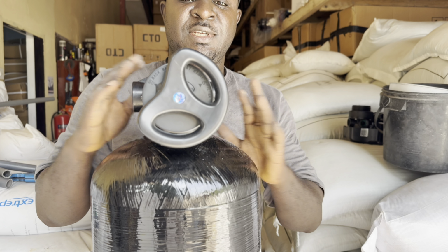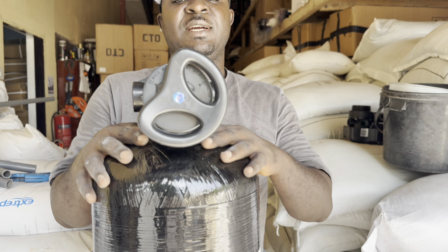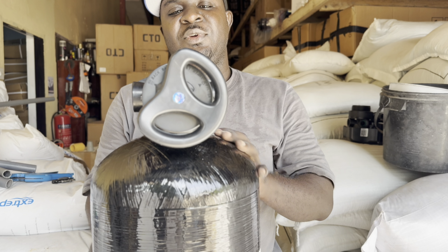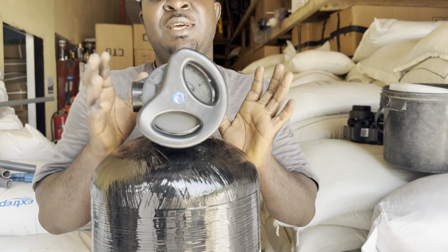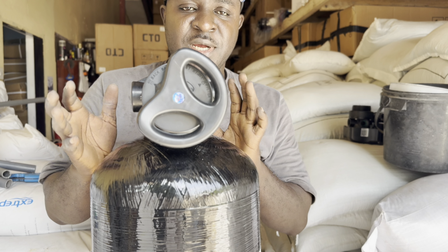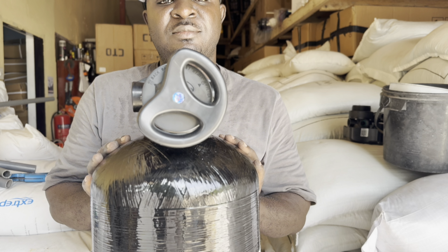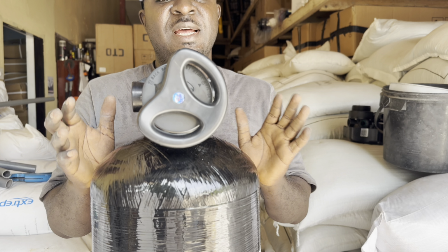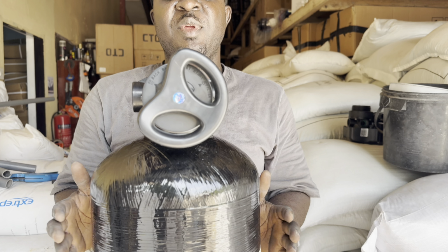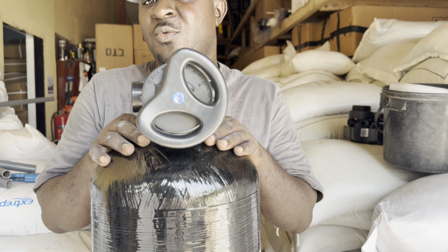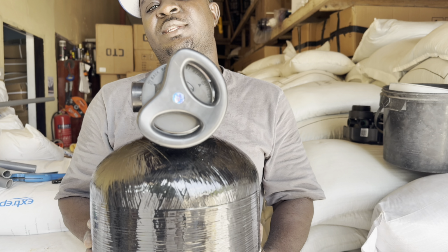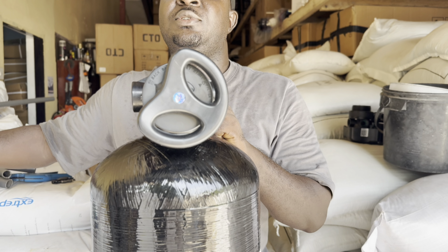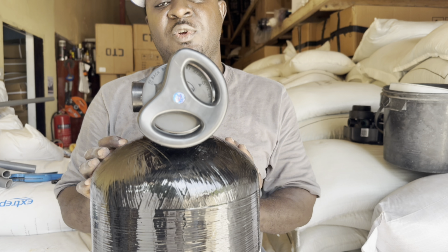So this is how to fill your multimedia tank to set up a multimedia filtration system for Ghana water or any municipal water that is turbid, and also you're trying to take care of the residual chlorine in your water. That's by using carbon. So basically that is how you do it, but whatever media you pour in the tank should be largely dependent on the quality of your water, what you want to treat and all that. Assuming your water is hard, you are going to use a softening system, right? You're going to use this kind of media and not what we have in here.